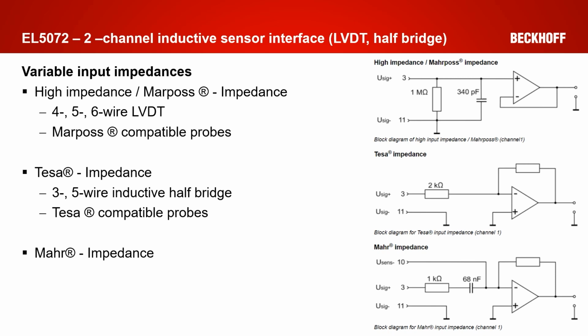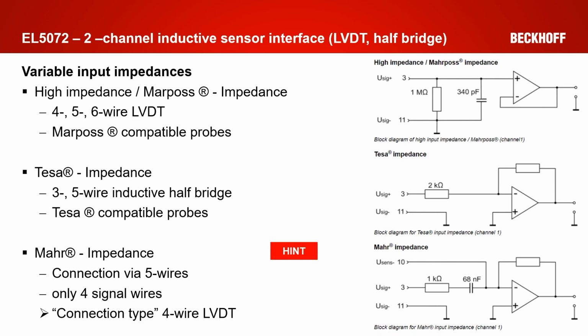Here, just a short hint from my side. It is a connection over 5 wires, but you have only 4 signal lines, so 2 for excitation voltage and 2 for the signals. The 5th line is the so-called virtual ground. Therefore, you need to choose on the connection type side the 4-wire LVDT.